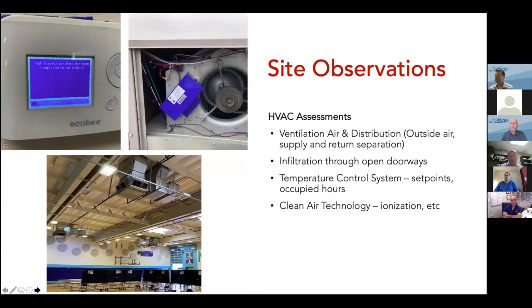So when we look at other things like distribution and building automation systems, you can see on the upper left the temperature was currently at 92 degrees. Obviously the system was off, and since the classroom was unoccupied, it was essentially let go to whatever temperature was outside, which leads to some humidity issues in certain cases, and obviously high temperatures. The bottom photo is essentially what we're trying to prevent: supply diffusers and return right next to each other.